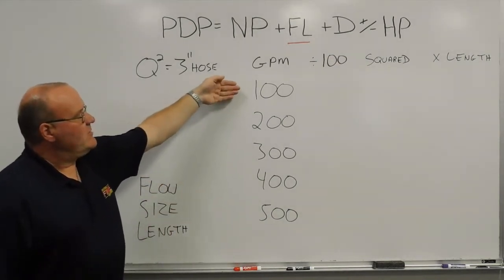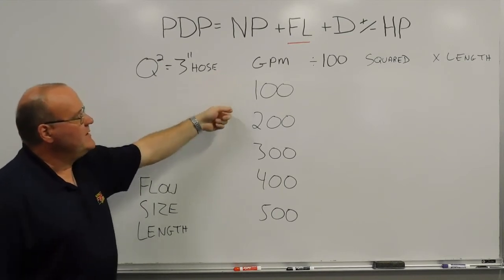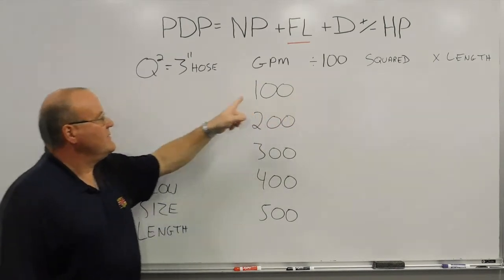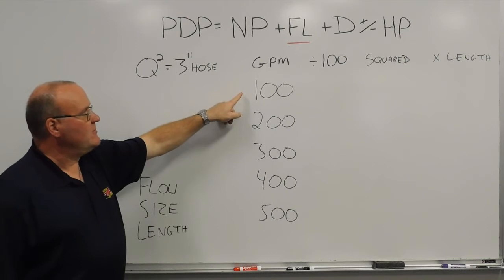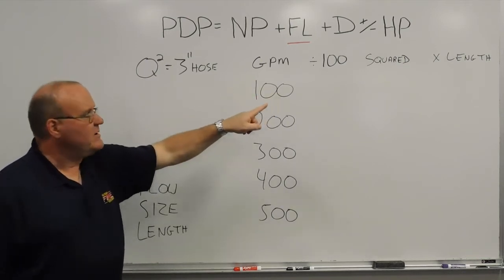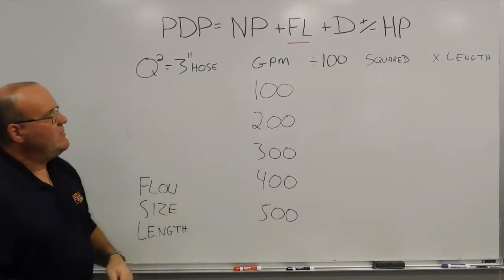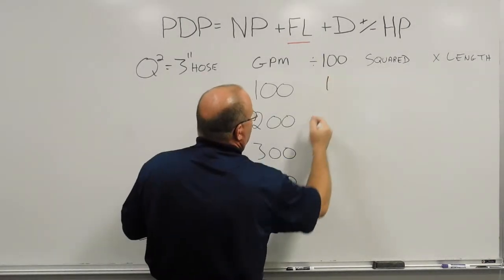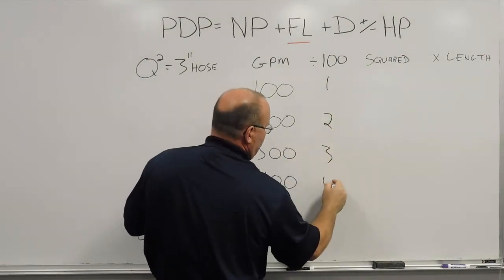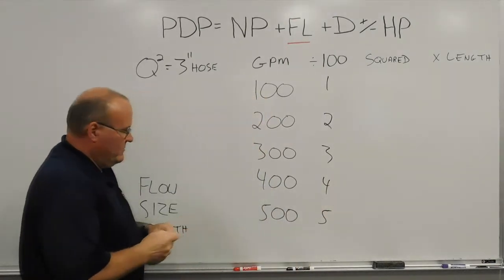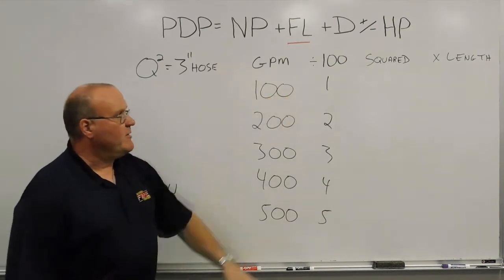The very first step: we start with 100 gallons a minute. The first thing we do to that gallon-per-minute number is divide it by 100 before we square it. So Q-squared — gallons per minute squared — starts with that GPM number divided by 100. So for all five: 100 divided by 100 is 1, 200 gives 2, 300 gives 3, 400 gives 4, 500 gives 5. Essentially you're knocking off the zeros of your gallon-per-minute number, and that divides by 100.